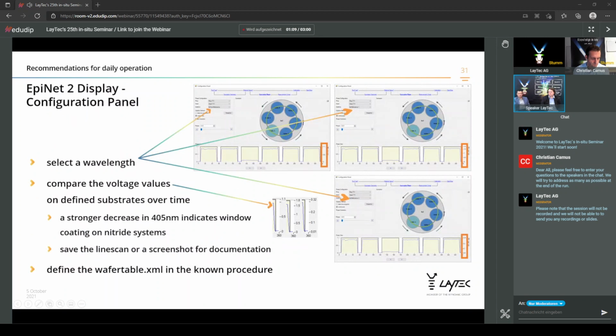Here you see the current software, the EpiNet 2, the configuration panel. So you select the wavelengths, you can compare the voltages as shown for all the wavelengths. For example, a stronger decrease in the 405 nanometers in the nitride process indicates that the window coating has started. The 405 nanometer is absorbed first. And you have the possibility to save the line scans, to make a screenshot for your documentation. Well, to define everything in the wafer table, Thomas will show that as well in the afternoon session. So this is a new procedure.